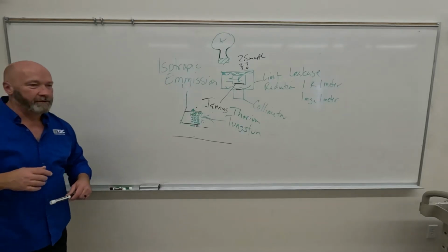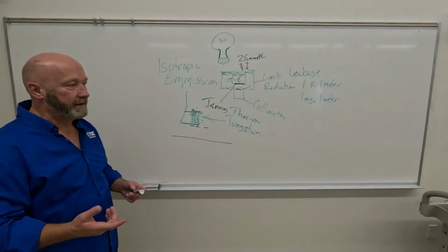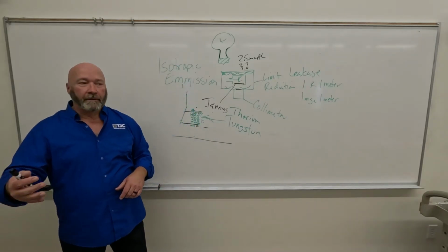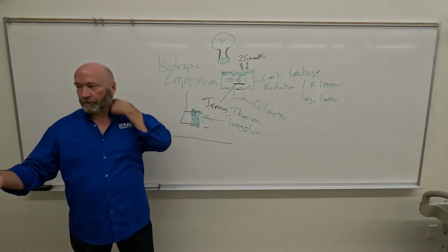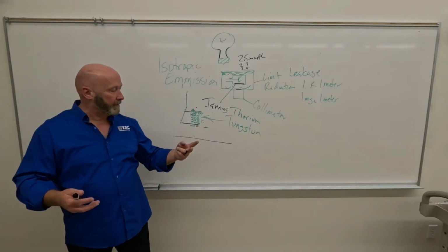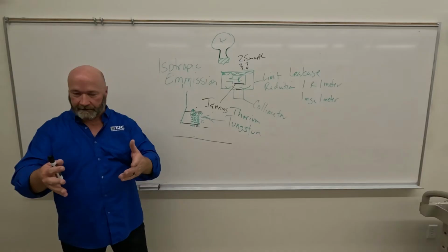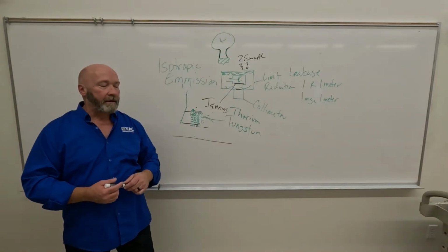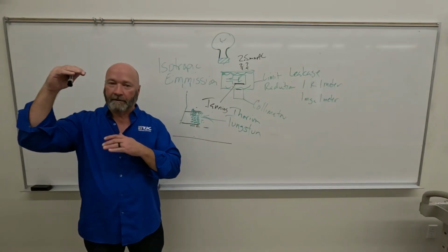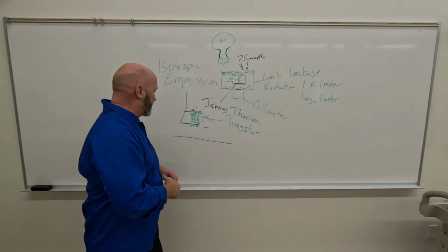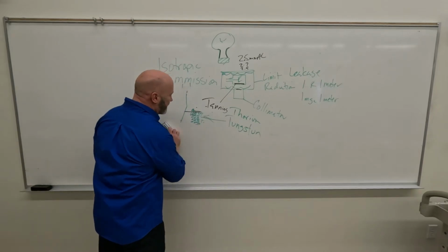Focusing cup. Okay, so filaments are usually side by side, you saw that. You're going to see in the Bushong that he does mention that some filaments are stacked. All of your X-ray tubes are going to be bifocal, meaning you have two filaments, right? So you've got a large filament and a small filament, and again, you saw that. But some of them will have, instead of the filaments being side by side, one on top of the other.